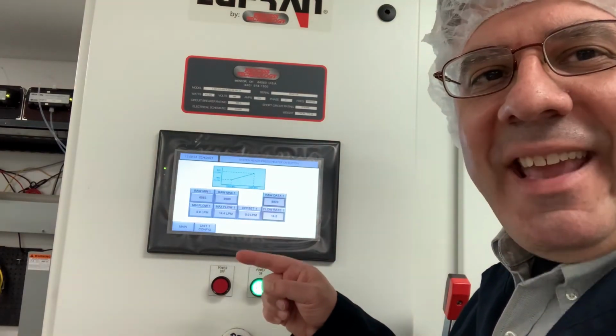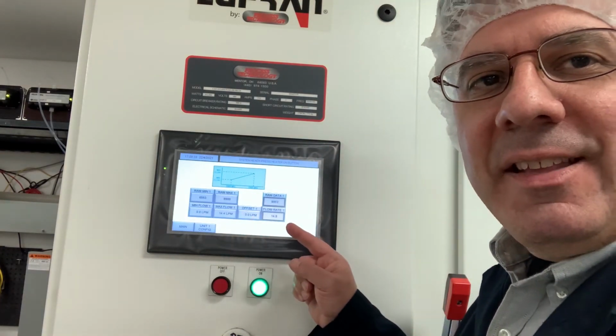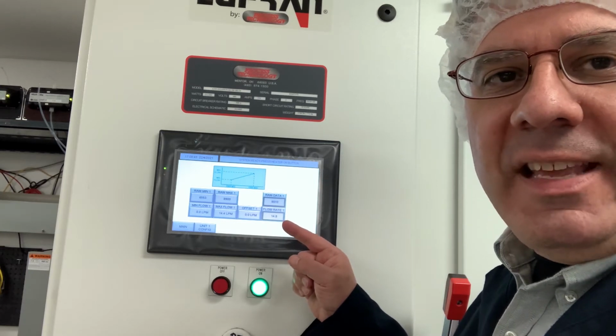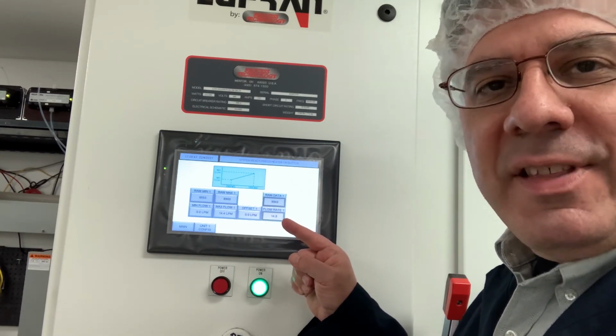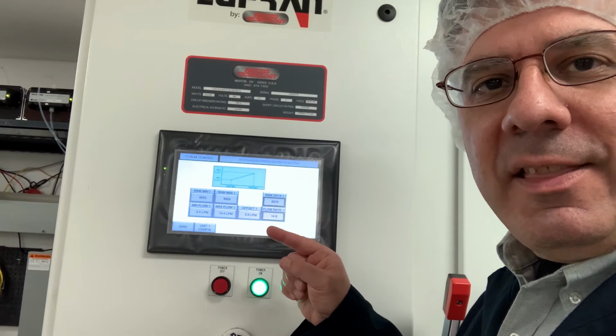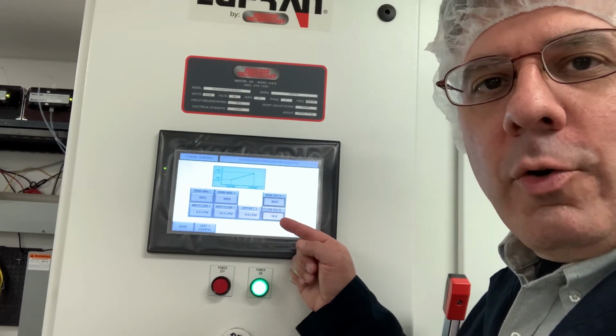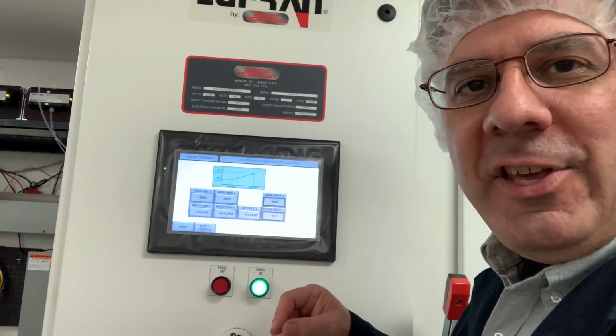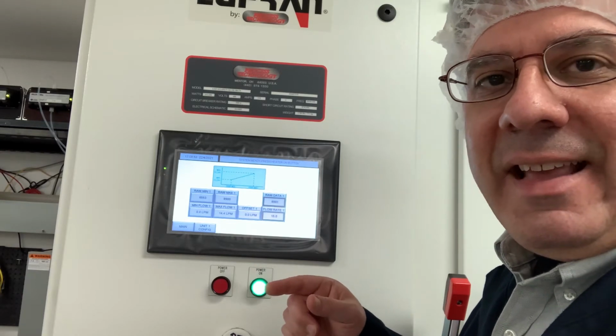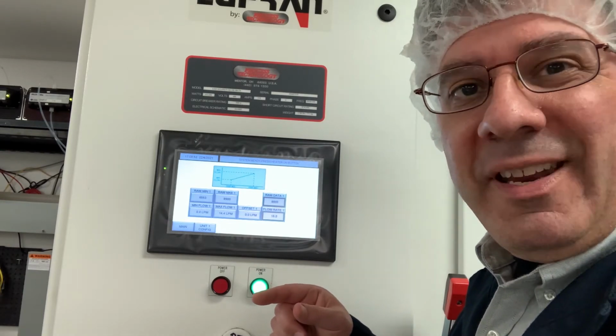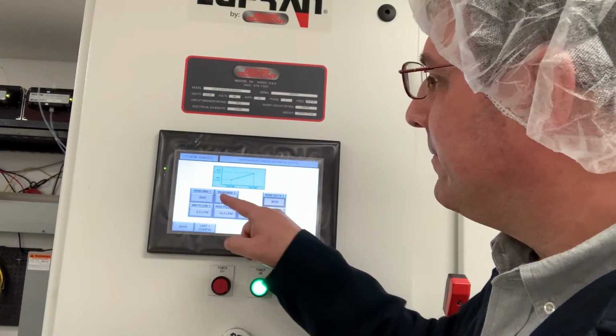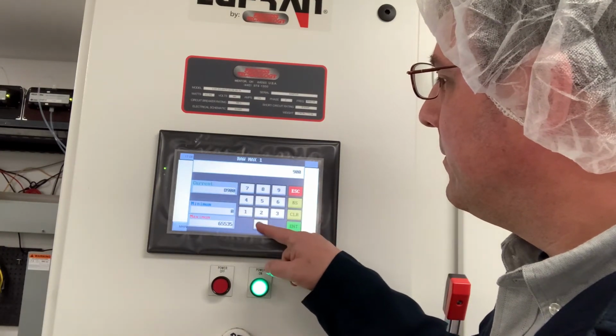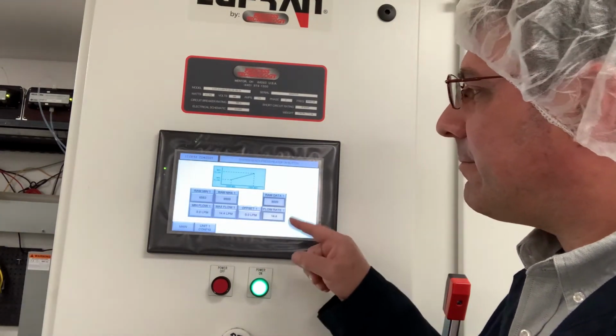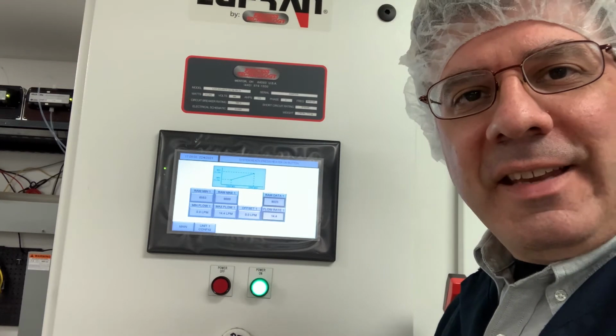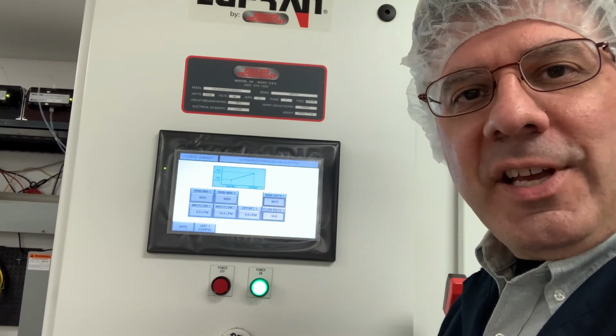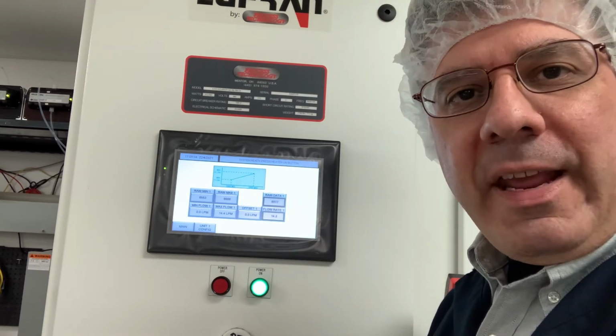I just changed it to 8,900, and you can see here your flow meter has gone up to 15 liters a minute. So that's how you're going to make adjustments here to get the value here to agree with your flow meter on the back of the unit. In this case, 9,000 was really close, so I'm going to use that. That's good. The next step involves adjusting for your lowest operating flow rate.